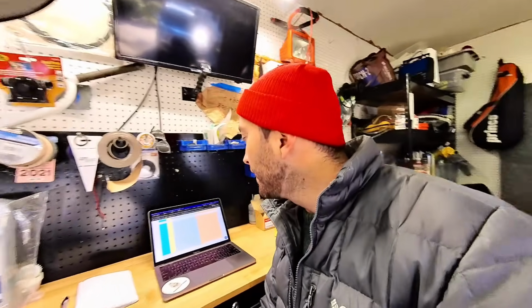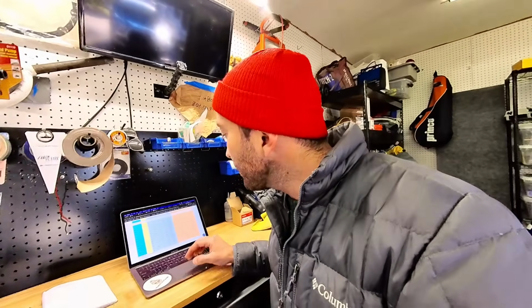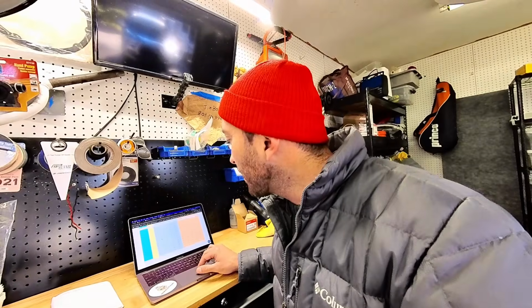Again, if we're erring on the side of being conservative, erring on the side of caution, you might go with a 40 amp breaker just to play it safe. Then you're guaranteed that that breaker is going to blow well before you reach any limits of the wire. So that's what we're going to do. I think a 40 amp breaker for this setup.